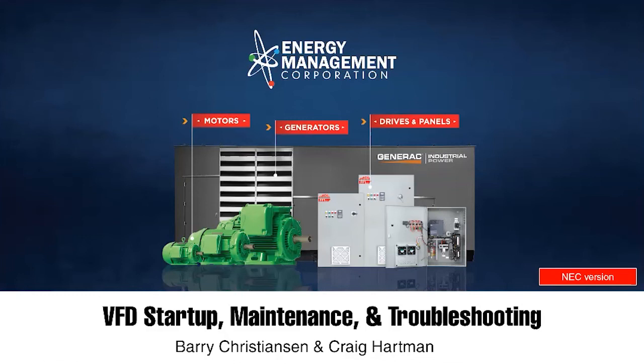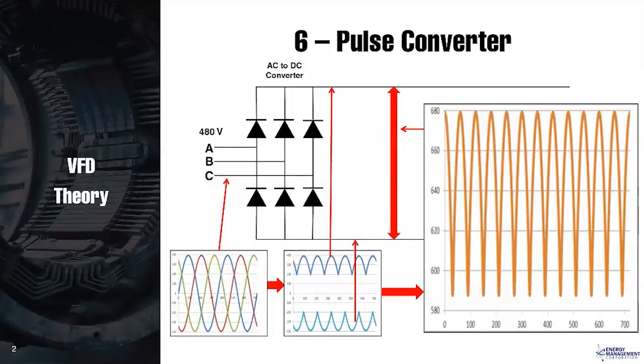So the first slide shows our AC to DC converter. And the AC to DC converter is composed of 6 diodes. I refer to them as check valves a lot of times. If you're not an electrical person, that's what they are. They just let the current flow in one direction. Now notice on this that if you put your meter between the positive bus, that would be the line on the top, sometimes labeled P for positive, sometimes labeled plus, whatever it is. You put your red lead there, and then you put your black lead on A. You are essentially measuring across the diode. And because the current's trying to go backwards, you should not see continuity. Now, if you simply switch your leads and put the red lead on A and the black lead on positive, then you should see continuity because now the current's trying to go through in the correct direction.